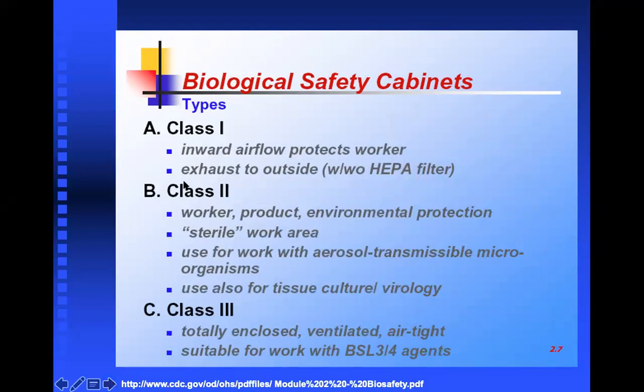Biological safety cabinets are mainly three or four types. Class one biological safety cabinets: inward airflow protects workers. That means airflow comes from the cabinet towards you, and exhausts to the outside. There is a HEPA filter for filtering any particulates and others. Class two cabinet: worker, product, and environmental protection. Sterile work area, used for work with aerosol transmissible microorganisms. Even COVID-19, SARS-CoV-2, most diagnostic labs use class two cabinets, used for work with aerosol transmissible microorganisms.